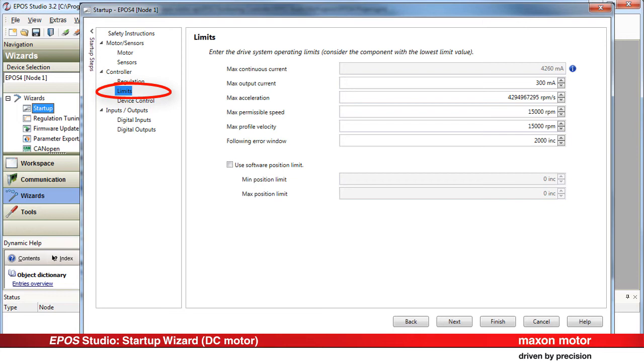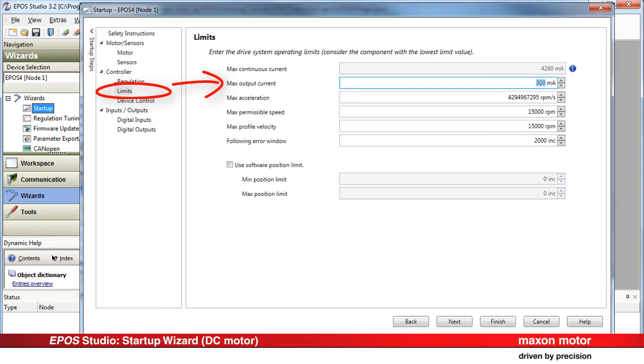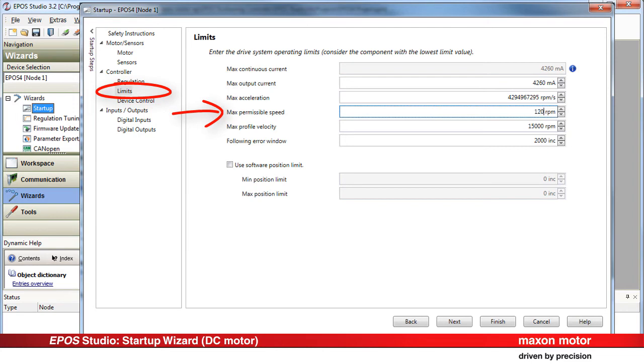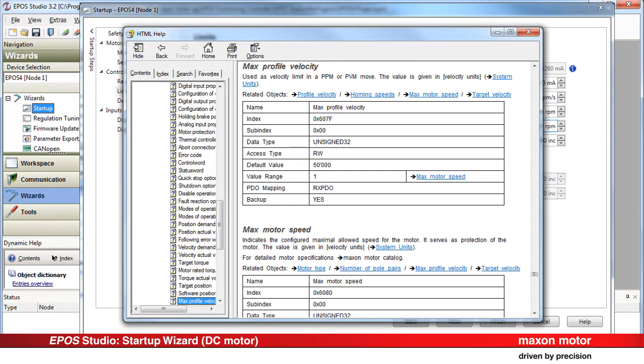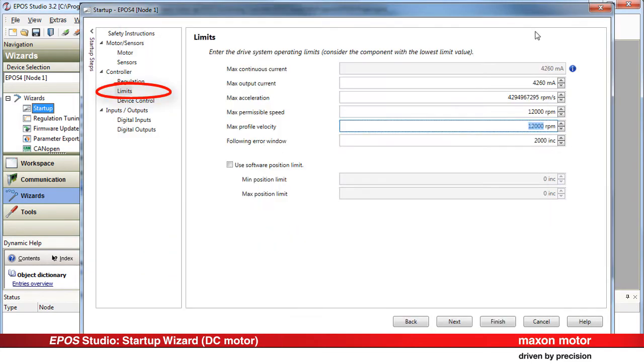Enter the drive system operating limits. Consider the component with the lowest maximum value. The maximum continuous current displayed here stems from the nominal motor current entered in the motor settings. In our case, we enter the values from the datasheet. Press F1 for detailed parameter description. Press Next.